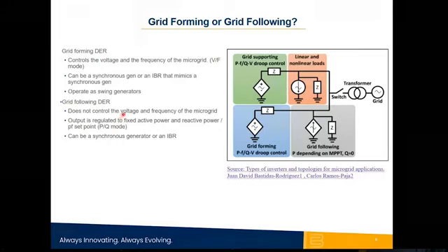And this kW and kVAR power factor set point may vary based on different inputs, whether it's over Modbus, an analog signal, contact inputs, logical inputs, etc. But they're regulated to a fixed active power and reactive power or power factor set point. And again, these can be synchronous generators or IBRs. And since the conversation is focused around synchronous generators, I just wanted to highlight that a synchronous machine, synchronous generator, genset, can be grid forming or grid following.